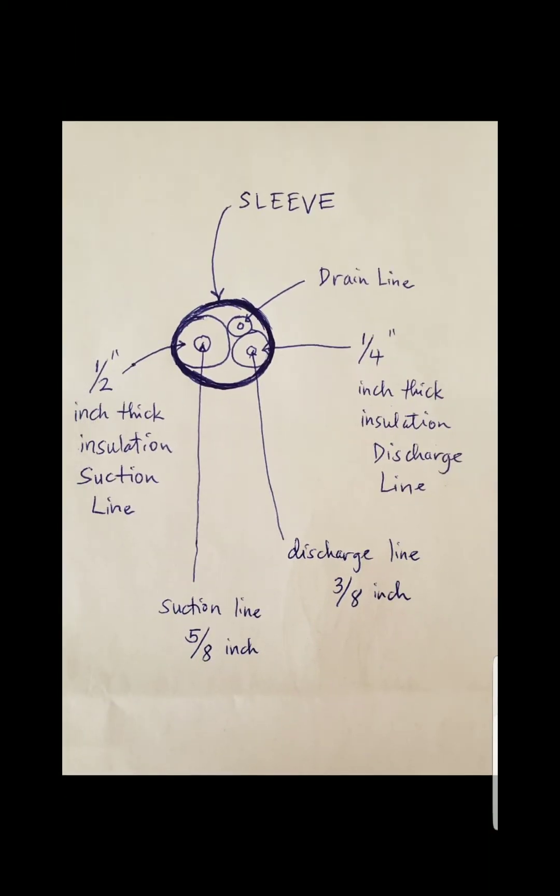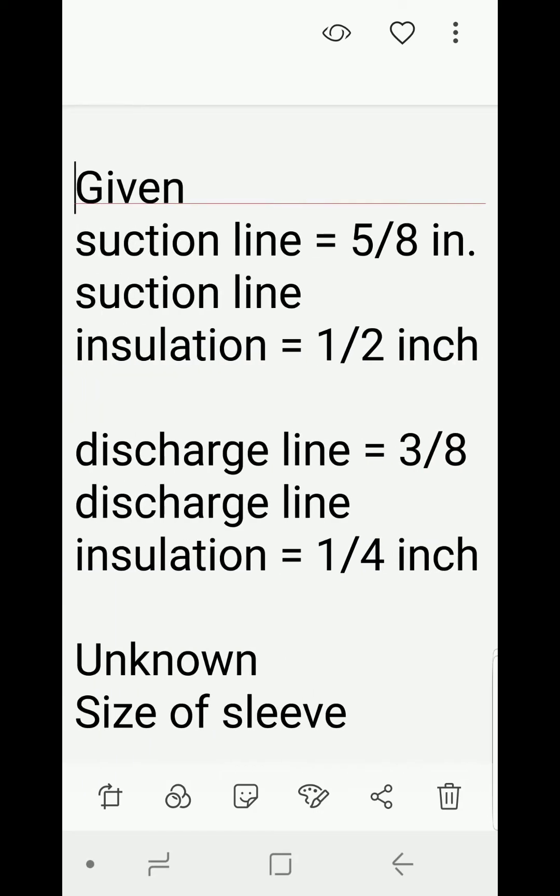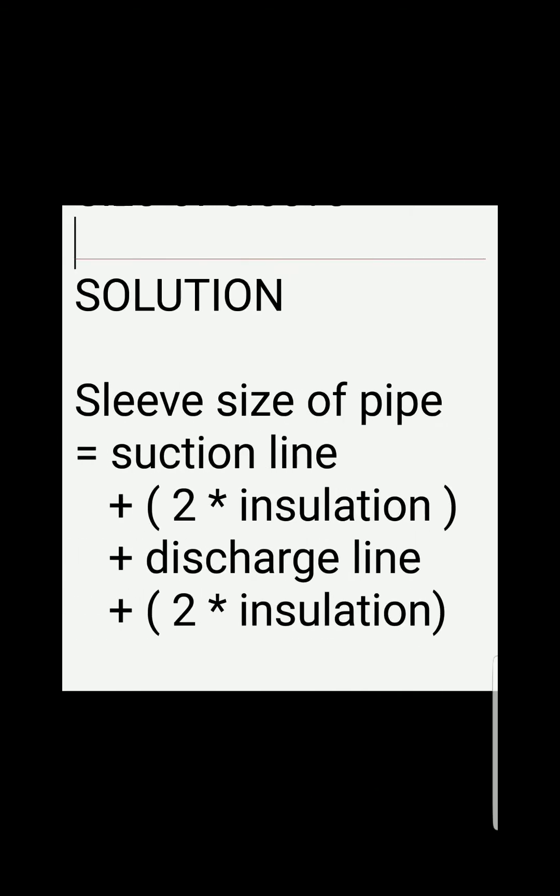Going back to the solution, we need to analyze first our given. So suction line 5/8 inch, suction line insulation half inch, discharge line is 3/8, discharge line insulation quarter inch, and unknown is the size of the sleeve.